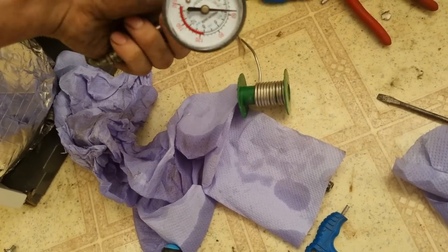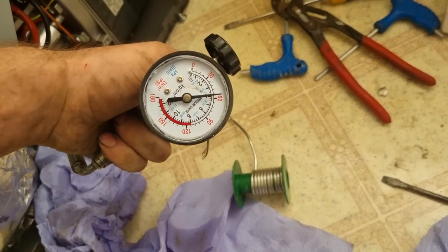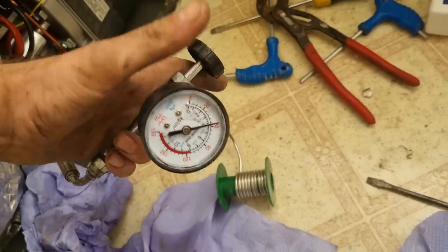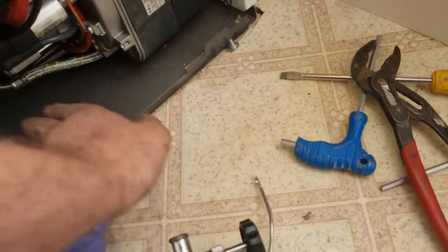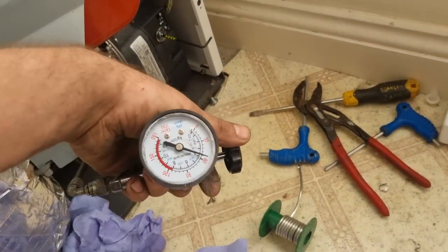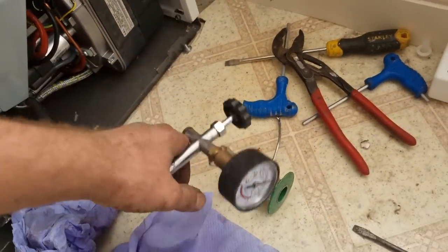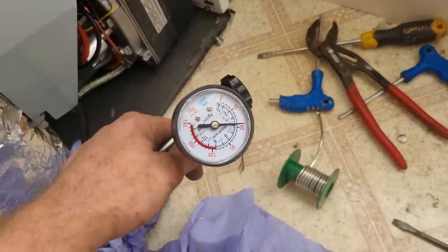I've got a problem with this oil pump. It was set at 60 out of the box, which is really rare for a Worcester. As soon as you set the pump pressure to where it should be, well, you can hear the oil pump rattling anyway. It's not running okay on 60 psi because obviously the ppm's are miles out. But as soon as you set it, I just spoke to the rep, he did actually answer his phone to be fair. He says he's never had it before.